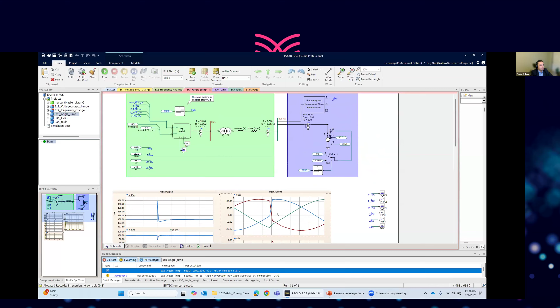I will jump to another test. We need to have an angle jump test as an example. When we have an angle jump, we can test here how well the PLL is working. You can see the source angle is changing 30 degrees. And you can see in the instantaneous voltage and current that we have this obvious jump. We can see the expected result: the power should not have much change here, and also the reactive power.